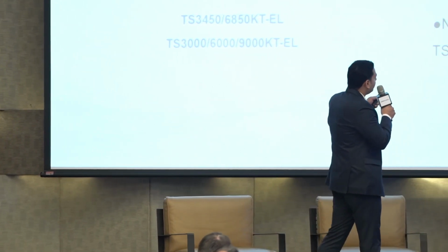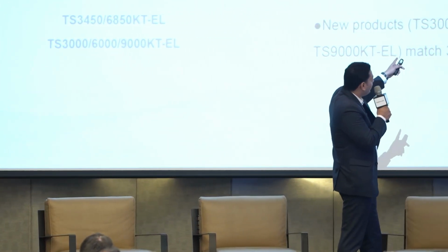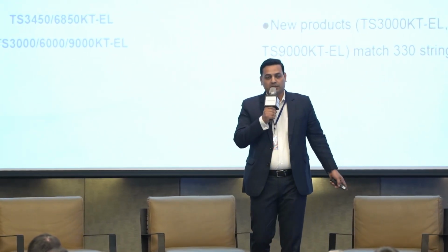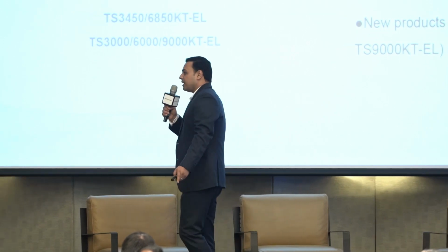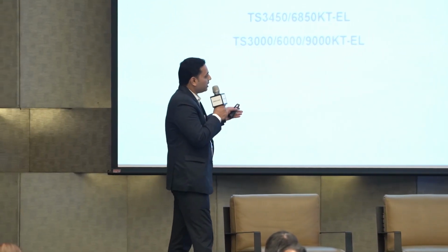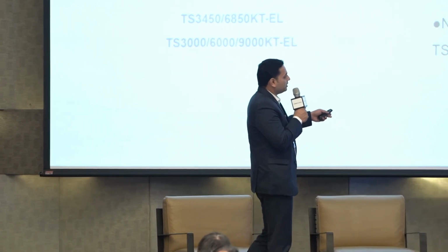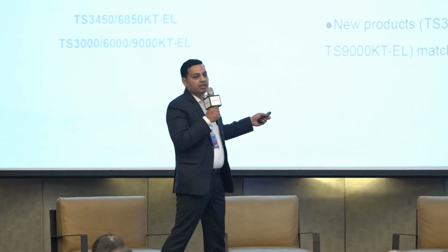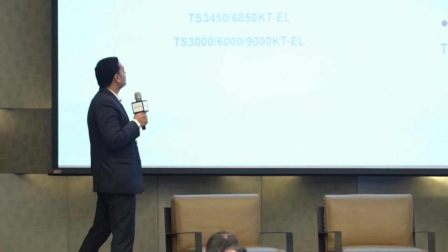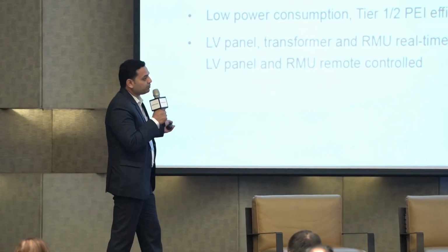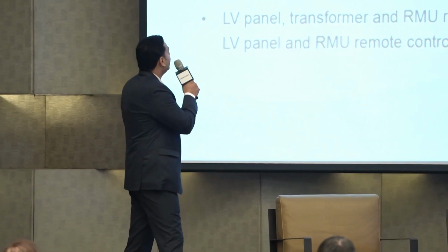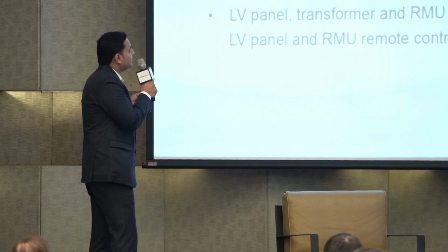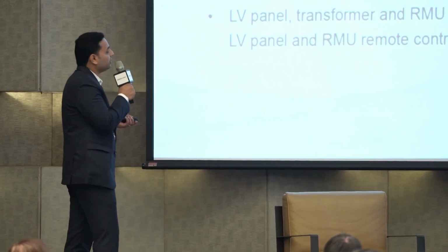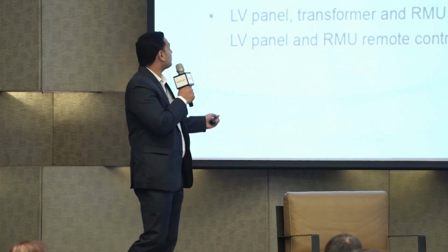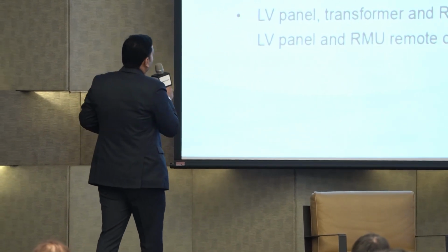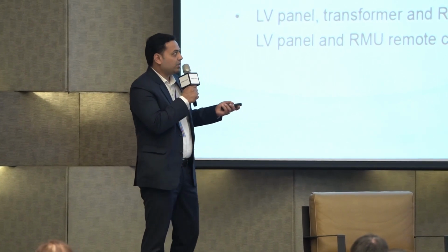For the existing 228 kilowatt product, we have two capacities: one is 3.4, the second one is 6.8 megawatt. For the new solution, which we discussed right now, 330 kilowatt string inverter, we are coming up with three capacities: 3 megawatt, 6 megawatt, and 9 megawatt. Now the advantage of these booster stations or integrated solutions is that they are prefabricated and pre-tested, which is very simple to install on site without any internal cabling required. And it's a standard 20 feet container, which is very easy to transport from one place to another.